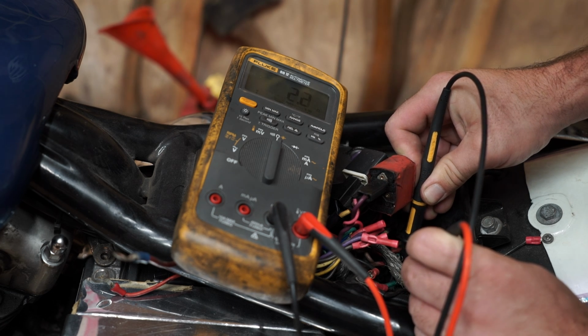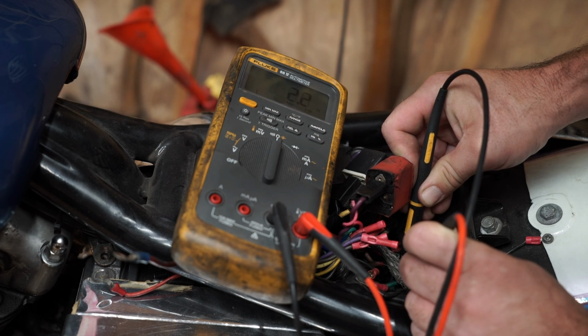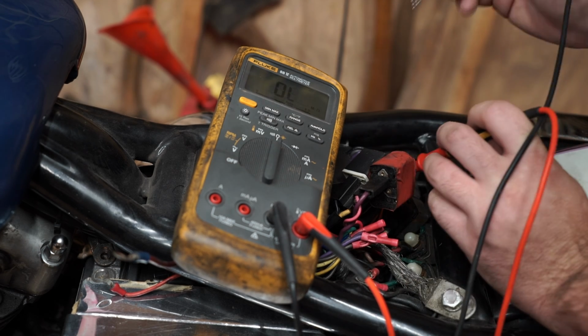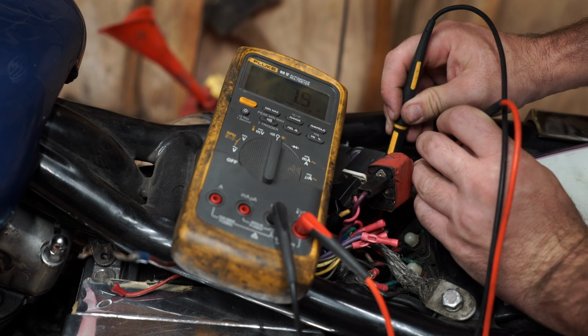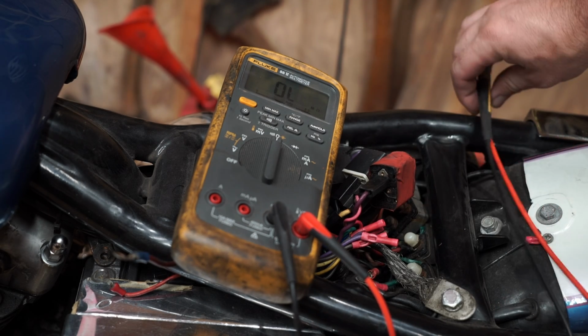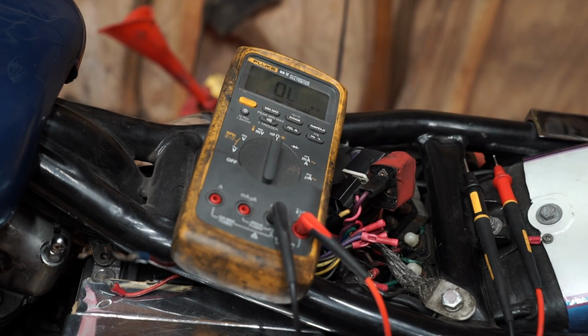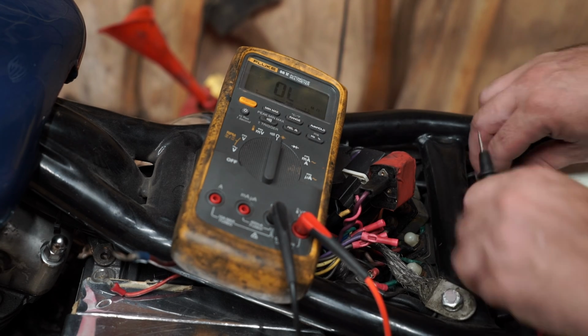If I can get my leads on it... yeah, that breaker's got 2 ohms across it, so we're doing better there on the charging circuit. On 1.2, I don't think we're really out of line on that. The nine-tenths of an ohm across the circuit breaker really looks pretty good.